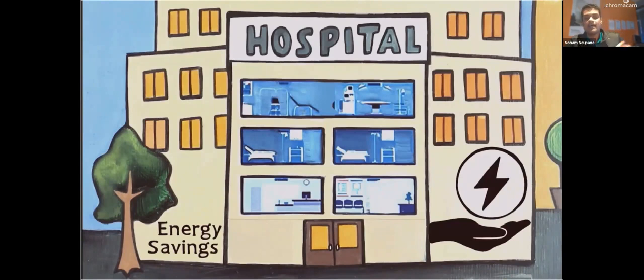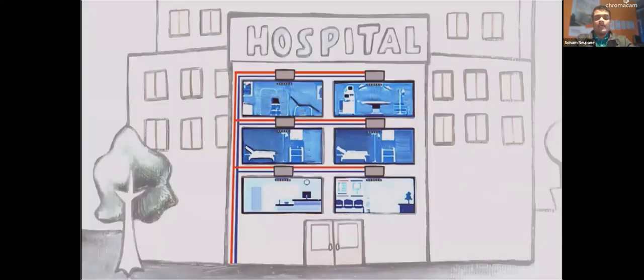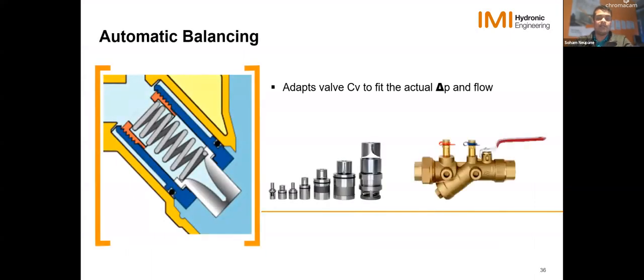So you don't really see the other parts of the system affecting the part you are actually currently looking at. You're working on one automatic valve, and no matter what other part of the system is doing, it's going to regulate that flow. What automatic balancing is basically doing is, it has this cartridge kind of mechanism that changes the opening of the valve, and it adapts the opening, this opening right here, the CV, to fit the differential pressure and the flow to make sure that you always maintain that constant flow.